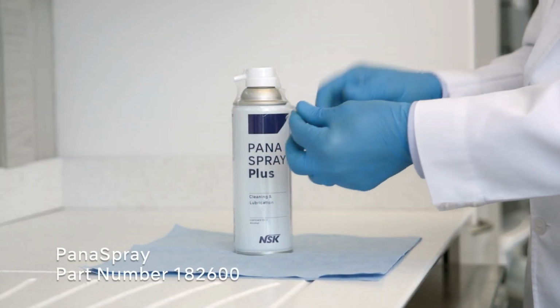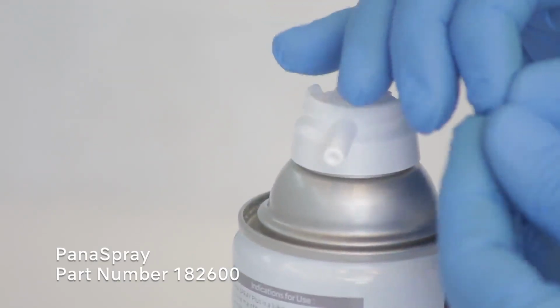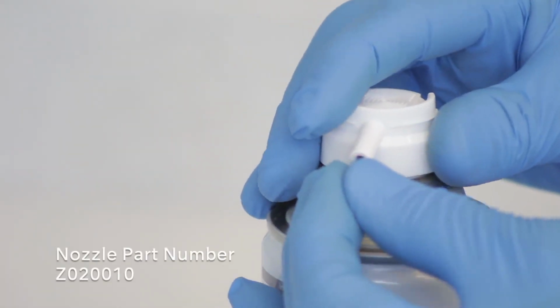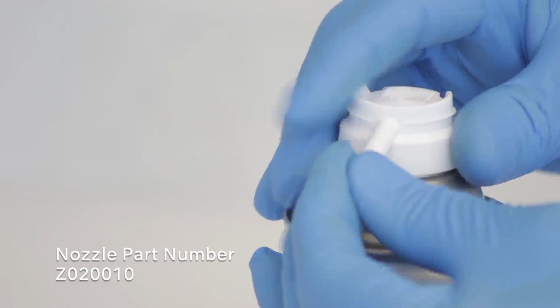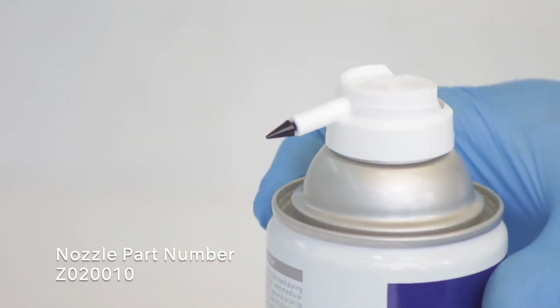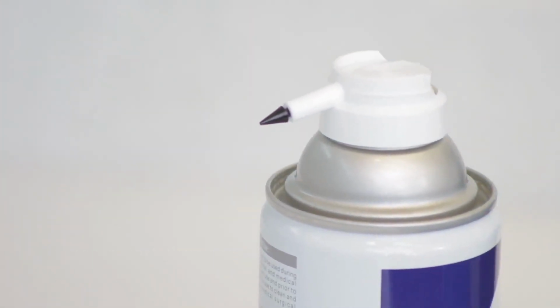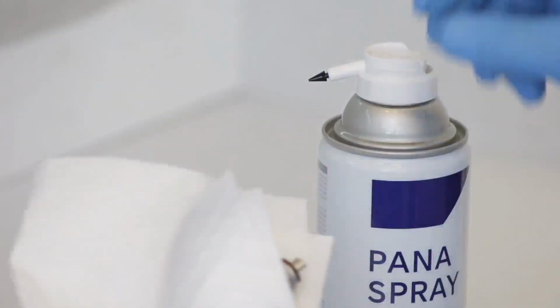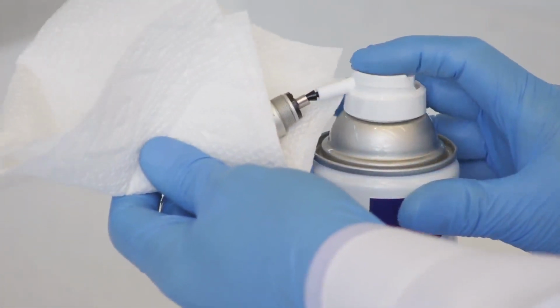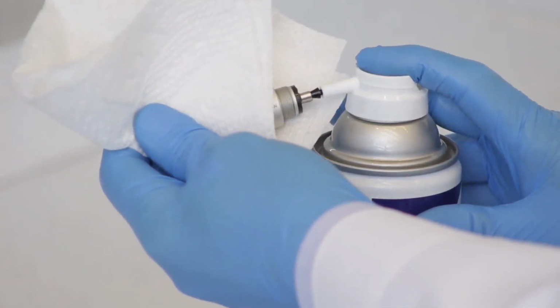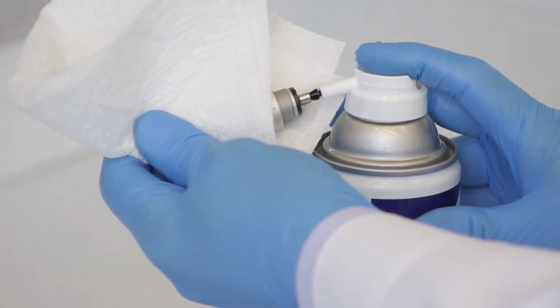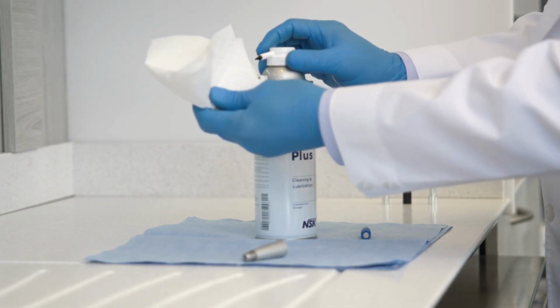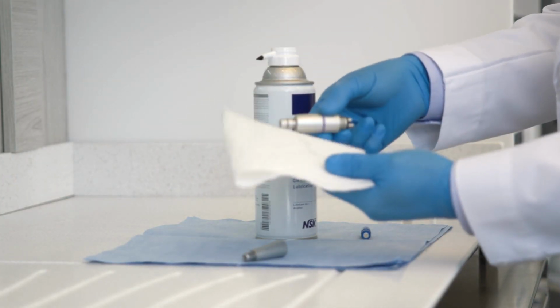Mount the spear-shaped nozzle that comes along with Panaspray and leave it on. If it's missing, you can order the nozzle using part number Z020010. Shake the can 3 to 4 times. Insert the spear-shaped nozzle in the drive air tube of the motor and spray for approximately 4 to 5 seconds after covering the insert joint, repeating the process if necessary until the outcoming oil is completely clear.